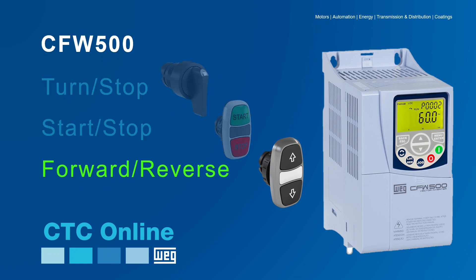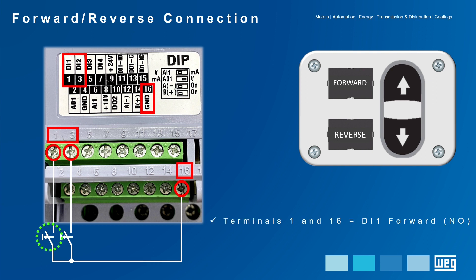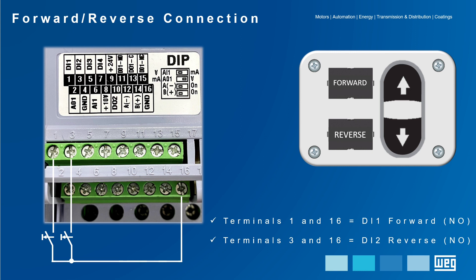Finally, we take a look at the FORWARD and REVERSE function. This command is the combination of TURN STOP with the turning direction. For this, you need two normally open contacts connected to digital inputs. One contact on digital input DI1 terminals 1 and 16, which will receive the signal from the UP arrow button for the FORWARD function, and another contact on digital input DI2 terminals 3 and 16, which will receive the signal from the DOWN arrow button for the REVERSE function. Note that for longer actuation periods, fixed selector switches should be used instead of push-button contacts.